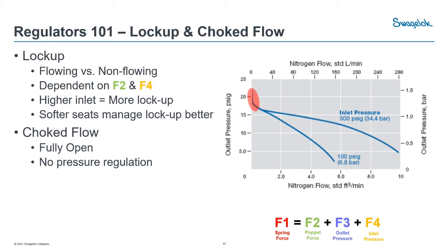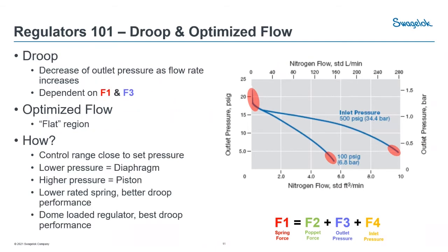On the flip side of this graph, we'll focus on choke flow. Choke flow is when the regulator is fully open — at this point you're not really regulating pressure; it acts more like a restrictive orifice. On both ends of this flow curve we really don't want to be operating. So where do we want to be? That moves us on to our next two segments: droop and optimized flow.